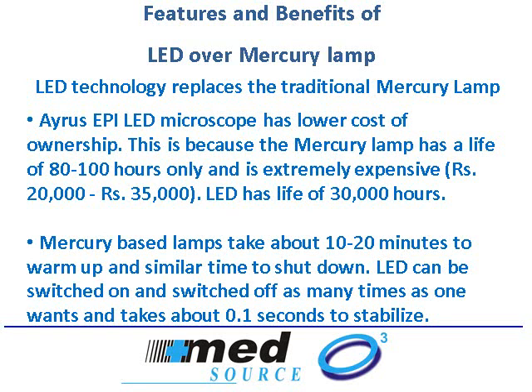So this means that if you're using an LED which has a life of about 30,000 hours, you will never pay money for servicing and for replacing these lamps every 100 hours. This is a massive advantage and the reason why today these microscopes have a very low running cost compared to the mercury based microscopes.